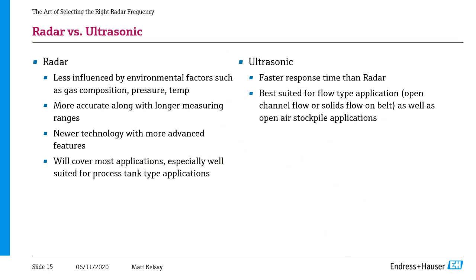So on the next, we'll look at when you might use a radar versus an ultrasonic. If you start on the left, looking at what's good about a radar, one, it's less influenced by environmental factors such as gas composition, pressure, or temperature. Like I said, an ultrasonic being a mechanical wave, it's calibrated to use in air. So if you've got a nitrogen blanket on top of your tank, an ultrasonic's not a good candidate because that signal is going to travel a different speed in that gas composition than it would in air.